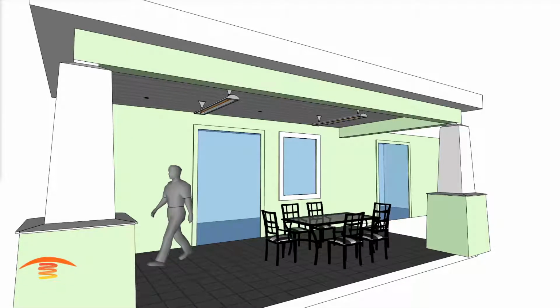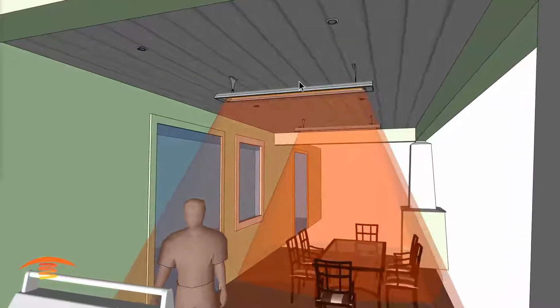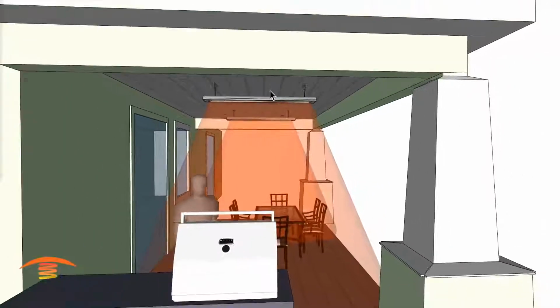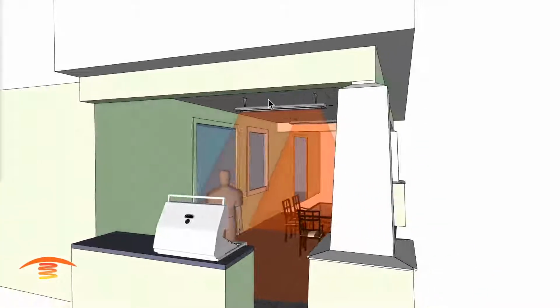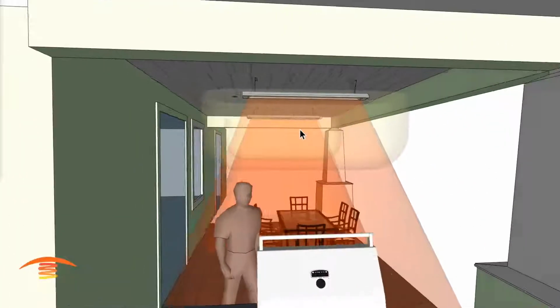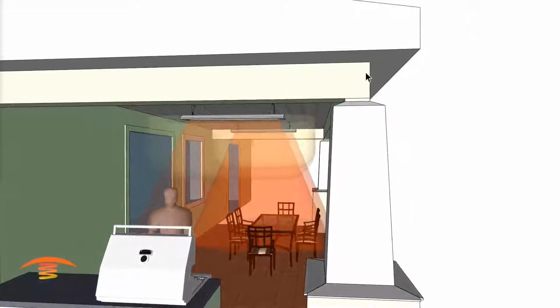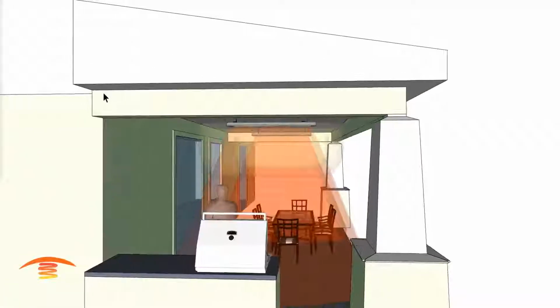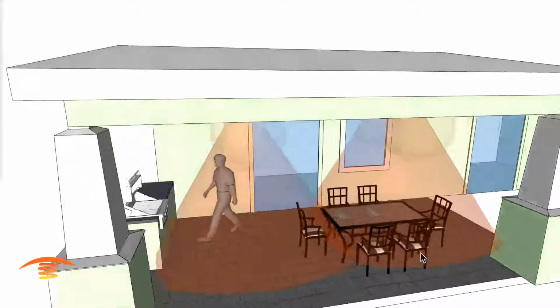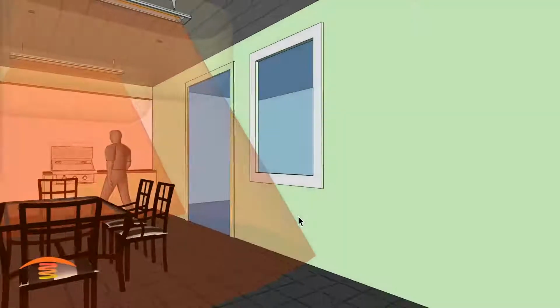If we turn the ray on, you can see with this mounting, it has 60 inches of clearance on top and 18 inches all around it. This is centered in the room itself, so I don't think we have any issues with clearances. Let's turn them on real quickly. You can see here and here, it's very clearly centered. Actually, I think I have it centered from this point out here to the inner wall, so we could move that a little bit. This is more of a walk space than a sitting space, but it could be utilized.